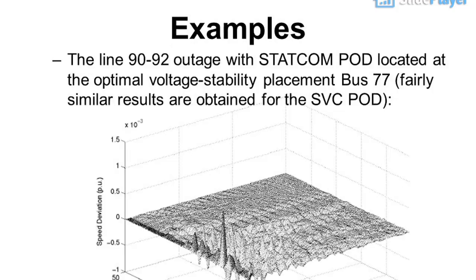The line 90–92 outage with STATCOM POD located at the optimal voltage stability placement bus 77 shows effective oscillation damping; fairly similar results are obtained for the SVC POD.